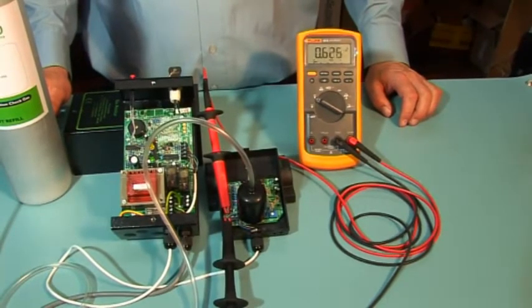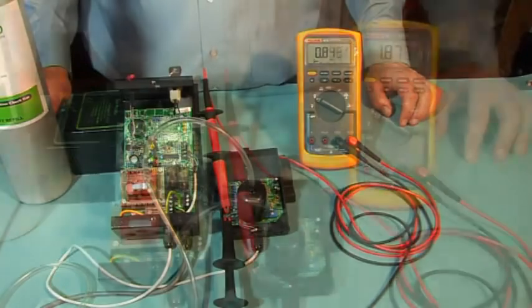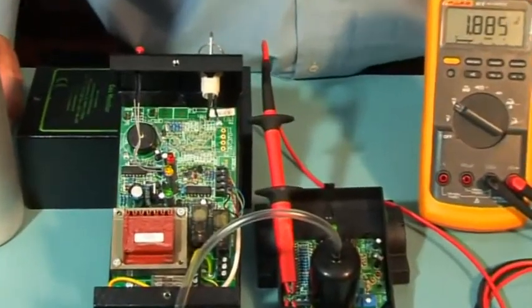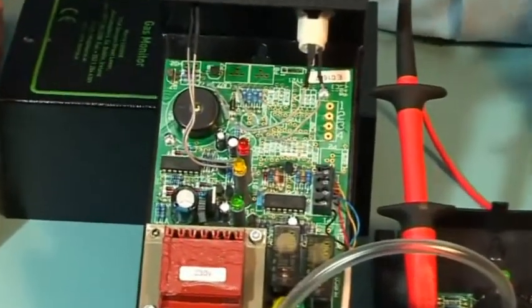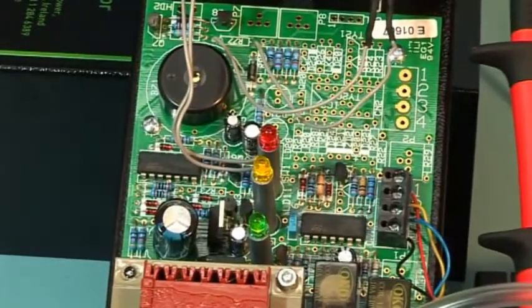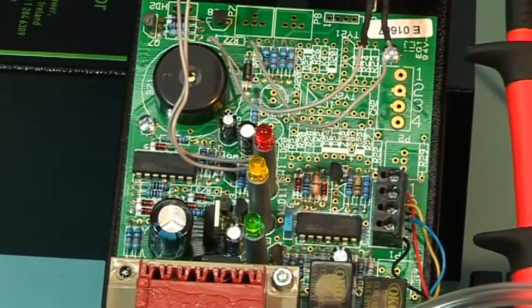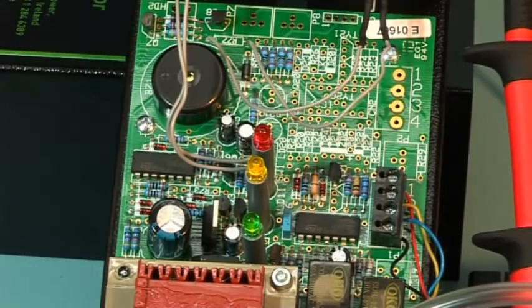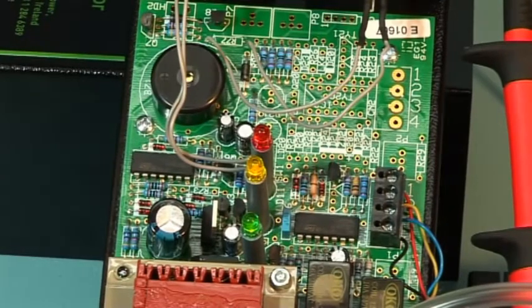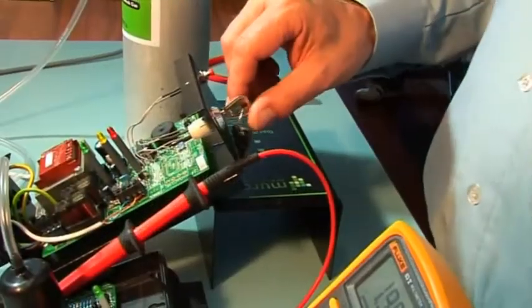Once you've reached the alarm set point, the low-level yellow LED will come on, and then the red LED will come on at the high-level set point, and the sounder, if enabled, will activate. The relays should also activate on the controller. The sounder can be muted by turning the key switch on the 2-level systems.